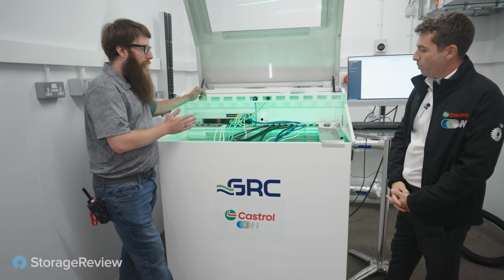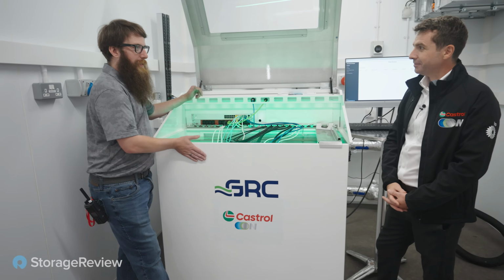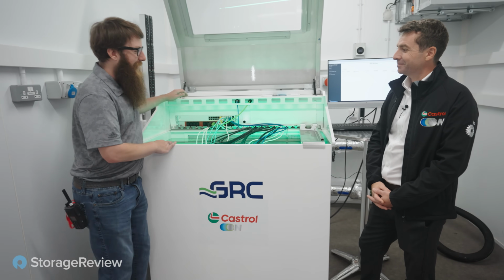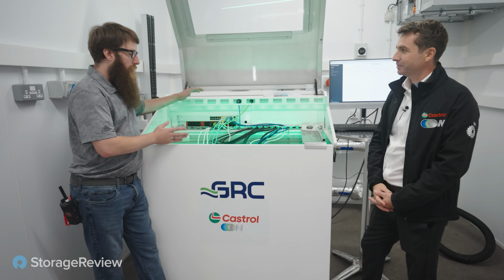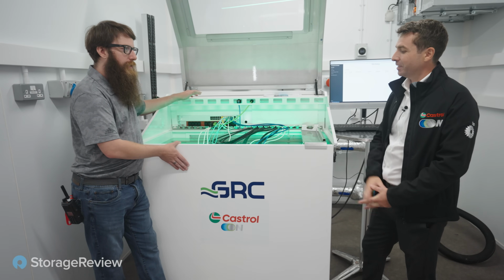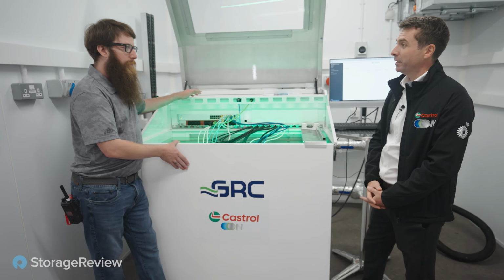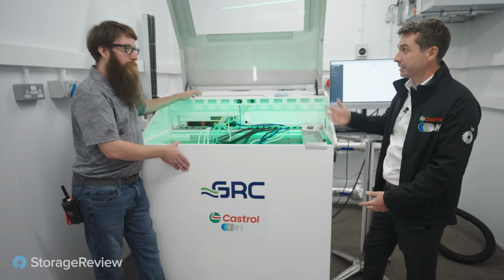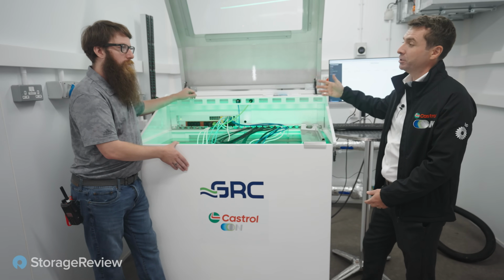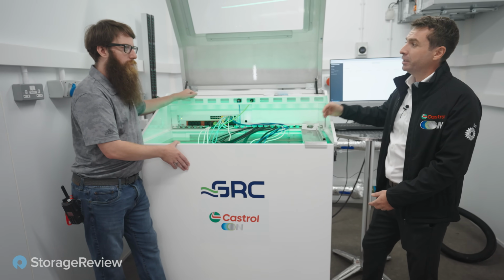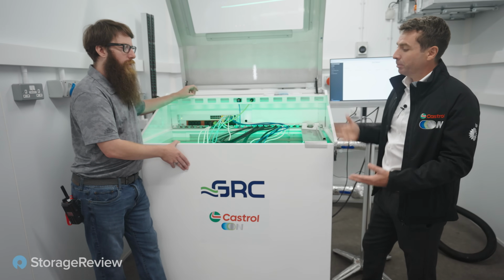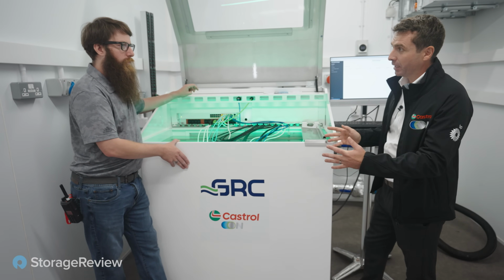So we've got the GRC tank here, it's a little warm to the touch actually, which is kind of nice, it's been chilly out today. What's the thermal capacity of something like this? So this tank can handle 50 kilowatts of power using high water inlet temperature. If you use refrigeration for a cold water inlet temperature, you can handle higher heat capacity, but for our scenarios it's set up as a 50 kilowatt tank.